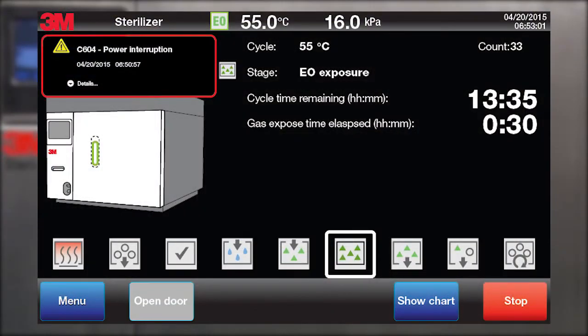The GS Series sterilizer touchscreen displays messages whenever a caution or an error occurs within a sterilization cycle. Cautions and errors appear above the image of the sterilizer on the display screen as a red outline box that includes a yellow triangle and exclamation mark, followed by a description of the caution or error. There's a toggle button within the red outline box that can be pressed to view additional information about the caution or error. A caution message indicates that an abnormal event has occurred. However, the sterilization cycle will continue. All critical parameters are still within acceptable levels when a caution message displays on the screen.